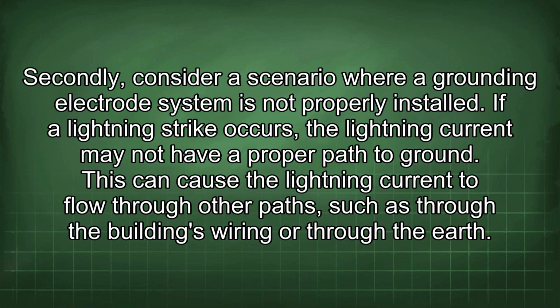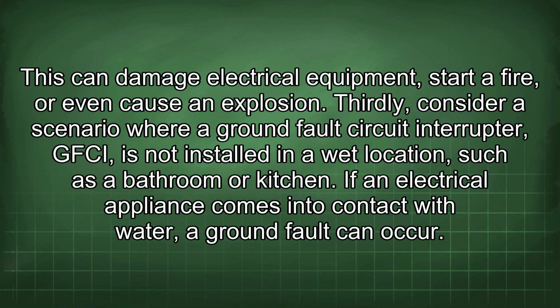Secondly, consider a scenario where a grounding electrode system is not properly installed. If a lightning strike occurs, the lightning current may not have a proper path to ground. This can cause the lightning current to flow through other paths, such as through the building's wiring or through the earth. This can damage electrical equipment, start a fire, or even cause an explosion.